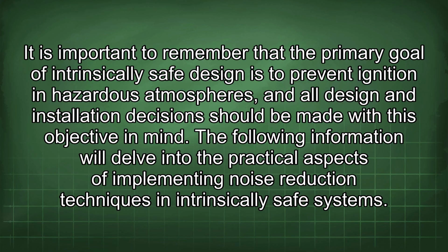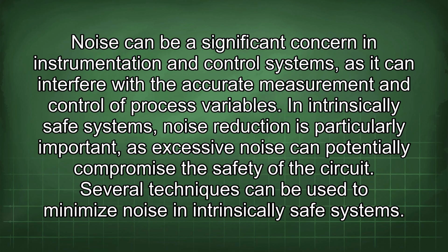The following information will delve into the practical aspects of implementing noise reduction techniques in intrinsically safe systems. Noise can be a significant concern in instrumentation and control systems, as it can interfere with the accurate measurement and control of process variables. In intrinsically safe systems, noise reduction is particularly important, as excessive noise can potentially compromise the safety of the circuit. Several techniques can be used to minimize noise in intrinsically safe systems.